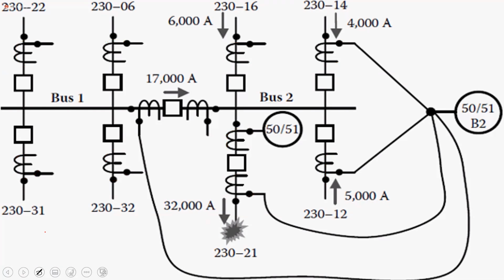What you need to take note of is that you now have an output from the CT, and you have a number in it: 50/51. Up here, you have 50/51. Now these are your relays. On your schematic, what you'll have would be your relay number. If you were to take up a one-line diagram for your system, they wouldn't show you the CTs, but you'll see these items with numbers in them, and they represent the type of relay being used. What we are seeing here would be overcurrent relays.